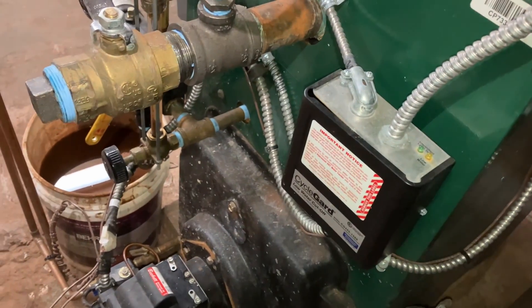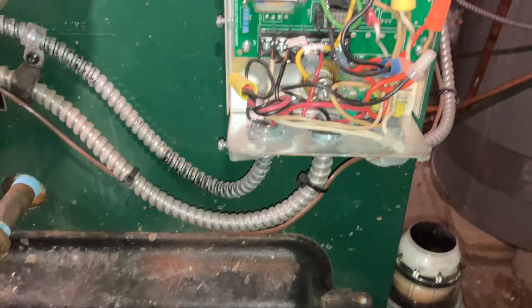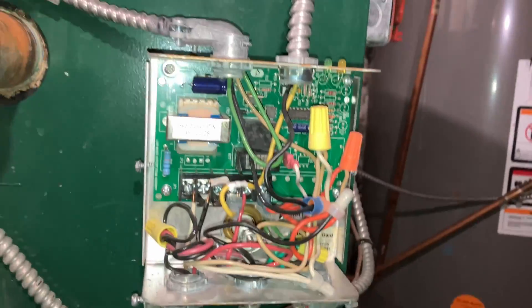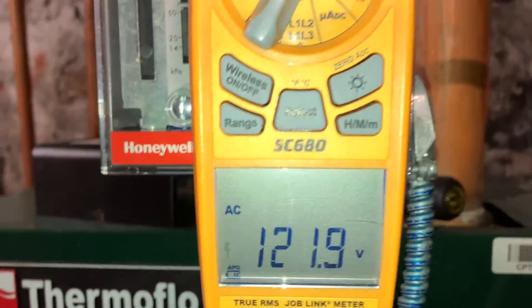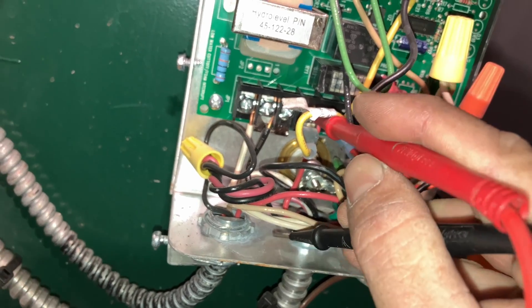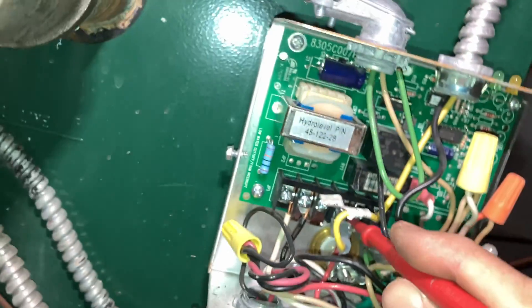Let's take a look inside the low water cutoff first, see what we got. Let's take this off and take a couple voltage readings to see what we're working with. Line voltage — 120, as we thought. We have 120 coming from our limit circuit.